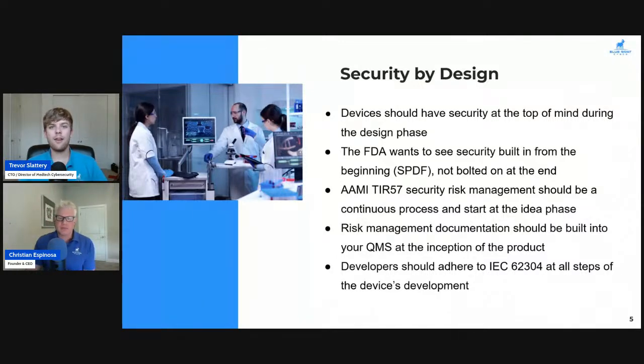We have these requirements. If we're testing them early, that is a requirement for the FDA. They need to see that you have security requirement test cases that have been implemented and verified. If we're doing this continually throughout the process, the documentation load and the burden on the manufacturer is greatly reduced when the time of submission comes. Very often, cybersecurity documentation is thought of as this big, daunting hurdle to cross at the end. And it's the newest major guideline. It's at the bottom of eSTAR. So it makes sense that it's often left towards the end. It's not always at the front of mind.